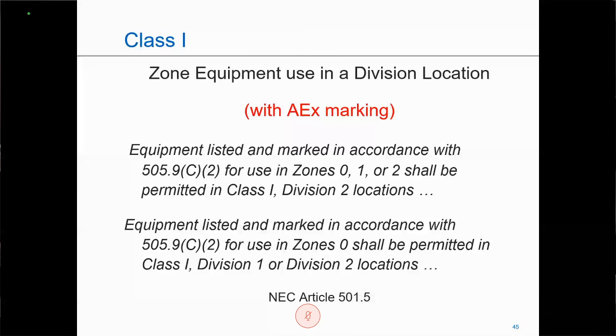One other addition: Zone 1 equipment may never be used in a Division 1 area. There's a difference in certification, a difference in testing, a difference in that so-called safety factor that I had mentioned previously. So Zone 1 equipment may never be used in a Division 1 area.